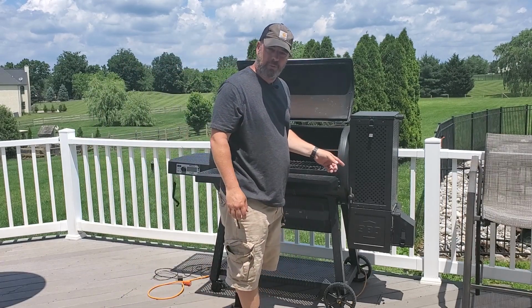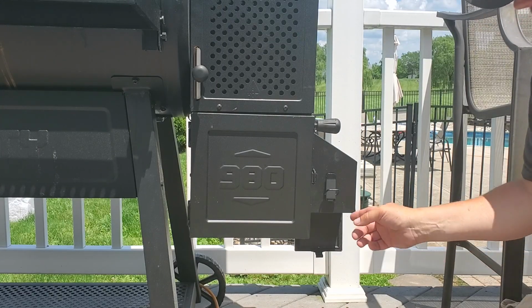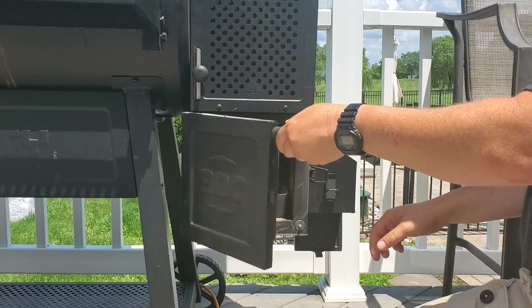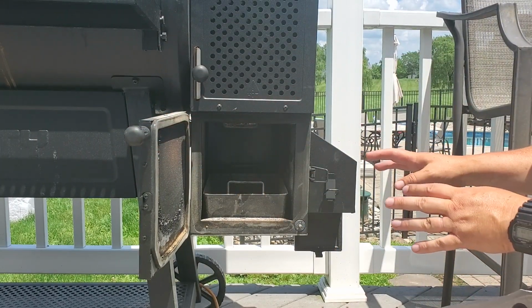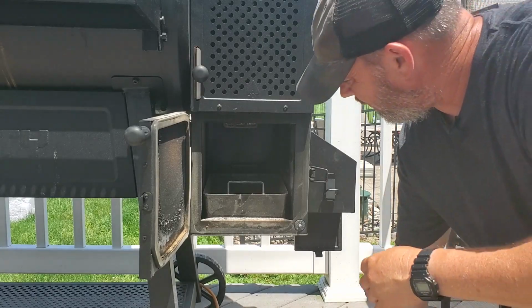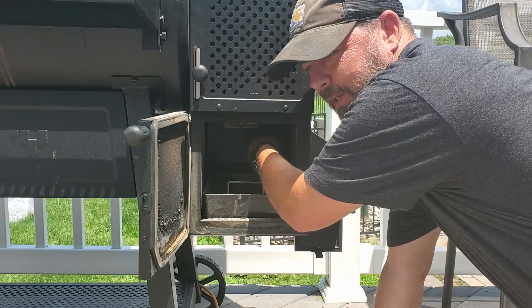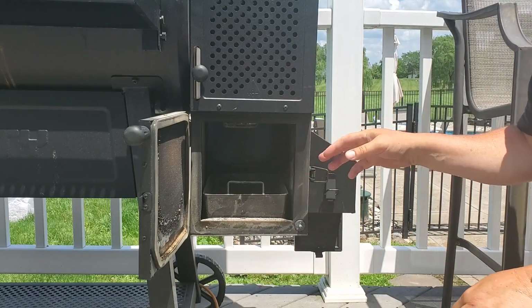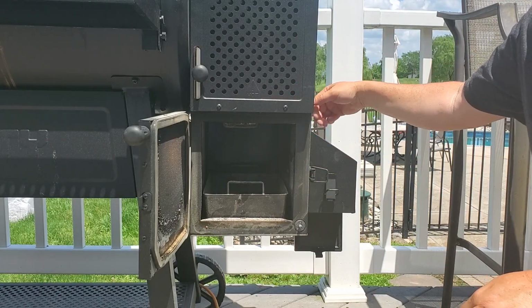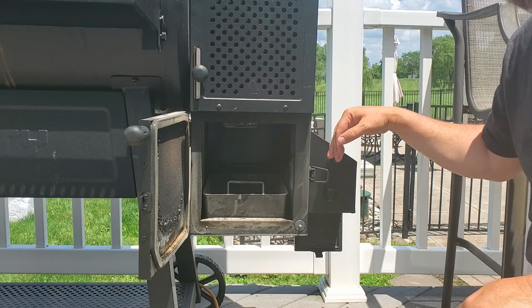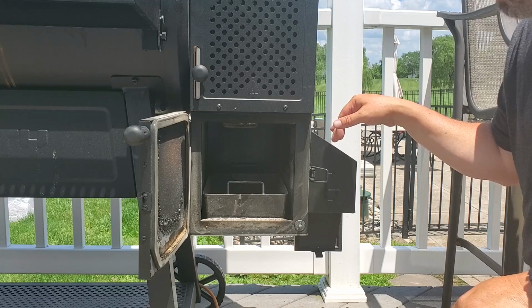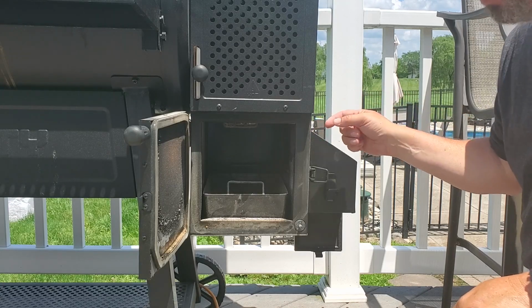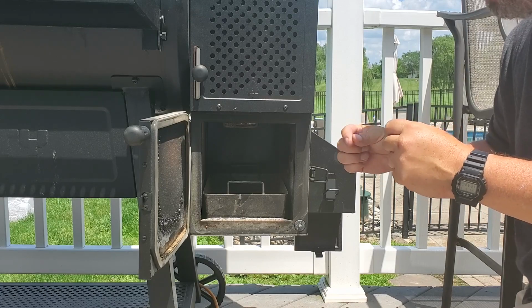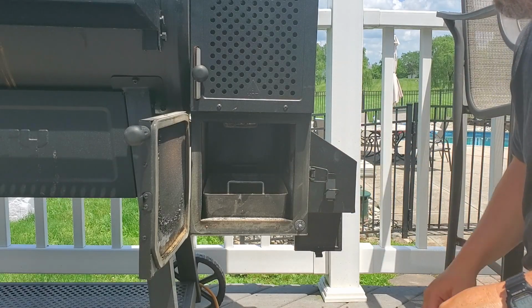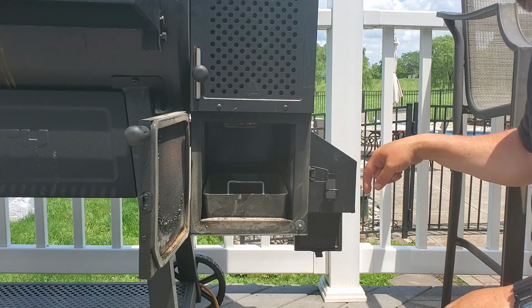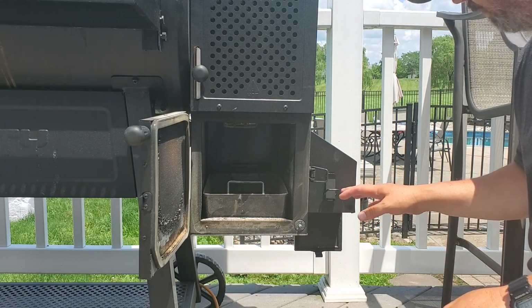You want to check things on this side as well. Once things are cooled down, don't open this if it's too hot. You can make sure your fan flap up here is hanging freely. There's a wire in the back here that the fan sometimes gets caught on, so make sure that's hanging freely. If it's not, pull it back so it is, and you can also loosen those screws a tiny bit to give it some play so it hangs nicely. You can also check your fan to make sure it's spinning freely and that nothing is in its way.